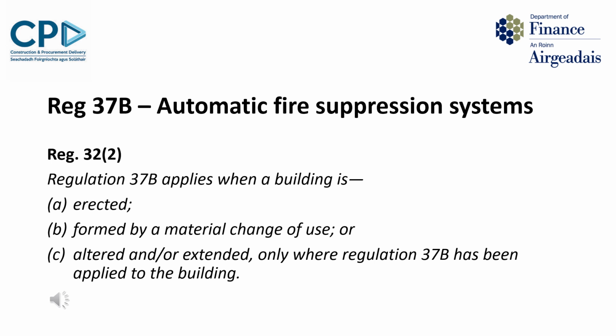The mechanism of Regulation 7, application to alterations and extensions in the building regulations, would not necessarily lead to having to provide automatic fire suppression to the existing building as well as the extension. The likelihood is, in most cases, it would not be required. Where we think it makes sense to ask for the extension to be fitted with automatic fire suppression is where the existing building is already fitted or being fitted with automatic fire suppression. Hence the wording of C in requiring 37B to a limited number of extensions and/or alterations.